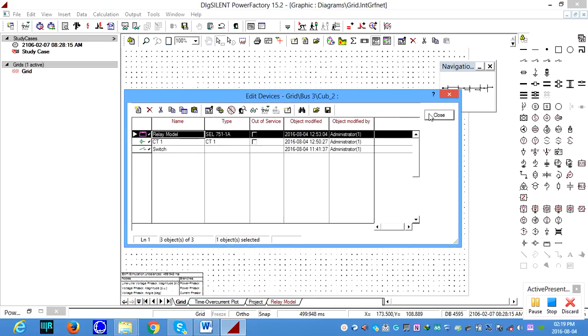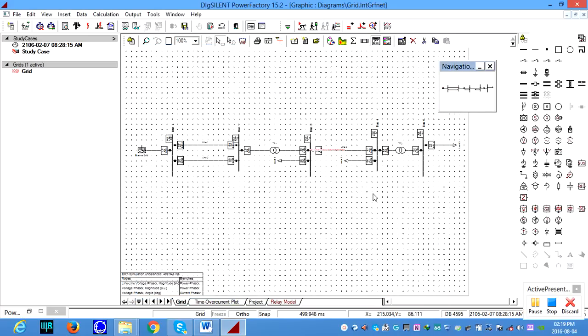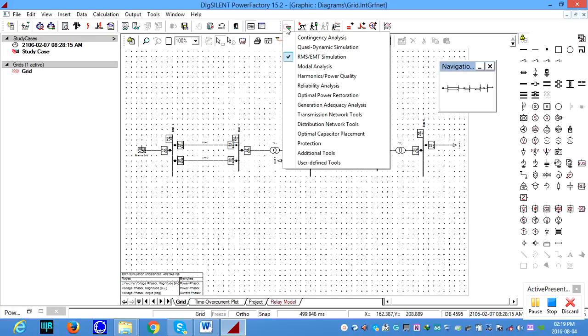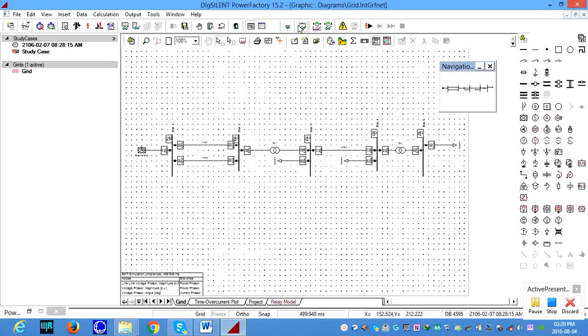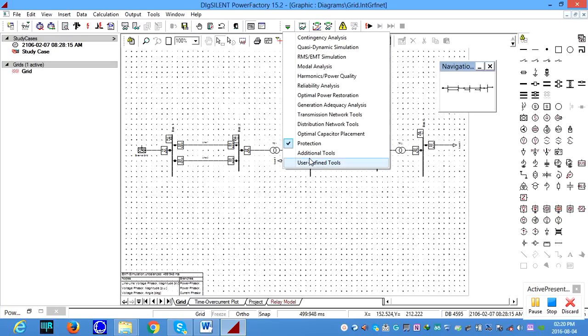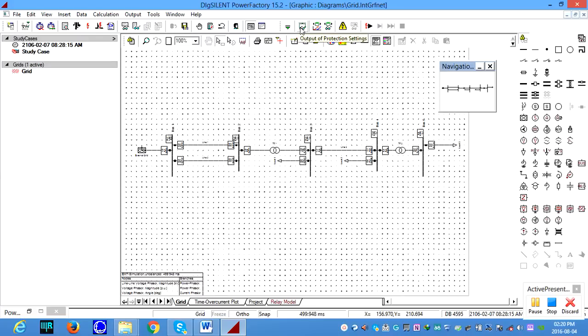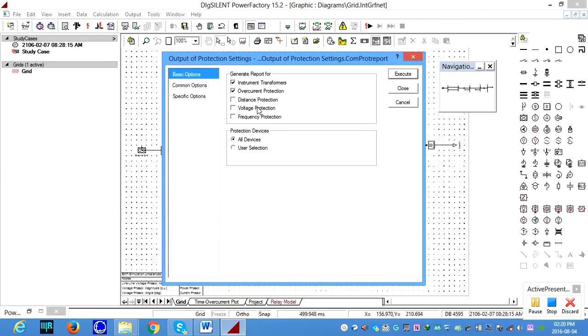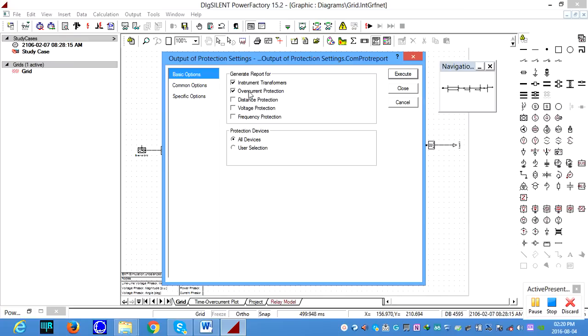And the next step, I also want to quickly show you how to export or copy the results in order to produce the report for your lecturer. For any case, you can export the results and store them in your database. For instance, if you want to generate the protection settings, in this drop-down menu you can go and select the protection. Next, make sure that you are in the protection. Next, there is an icon called output protection setting. If you click, in this case I want to see the instrument transformer settings and overcurrent protection settings. I can execute this file.